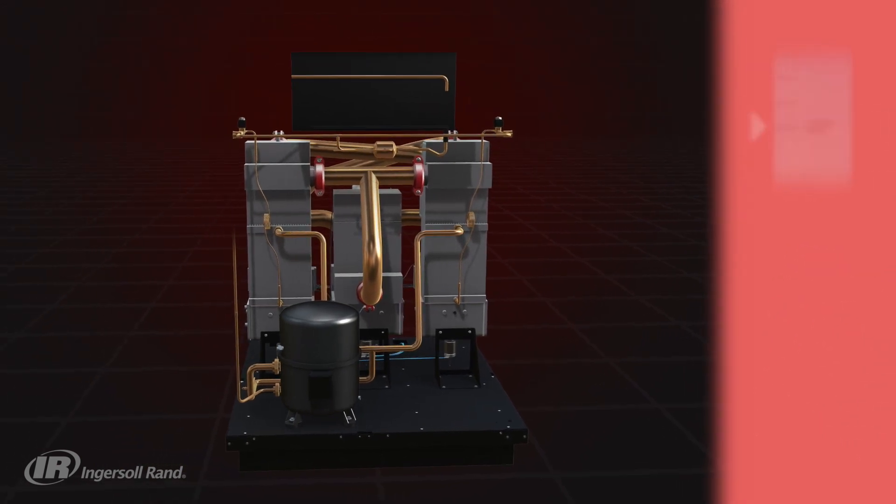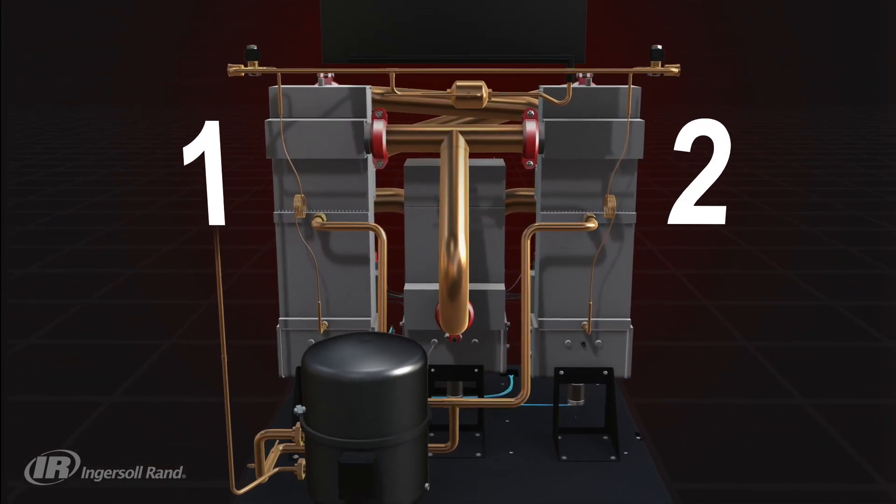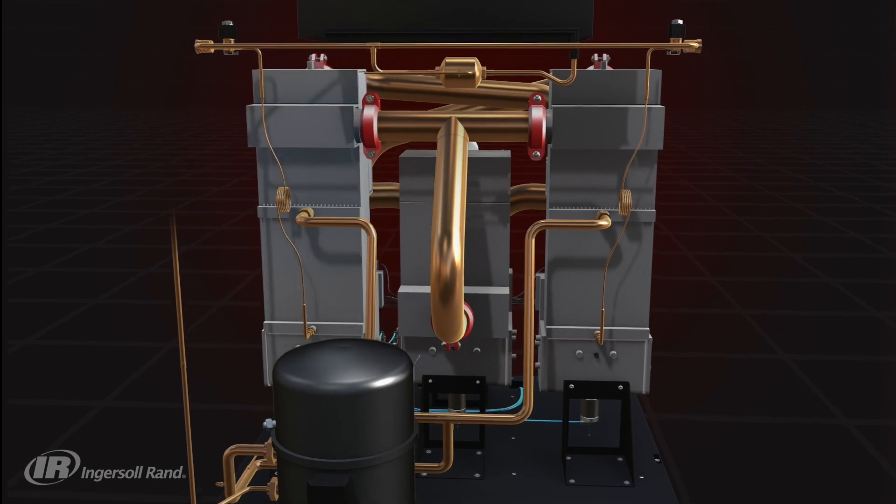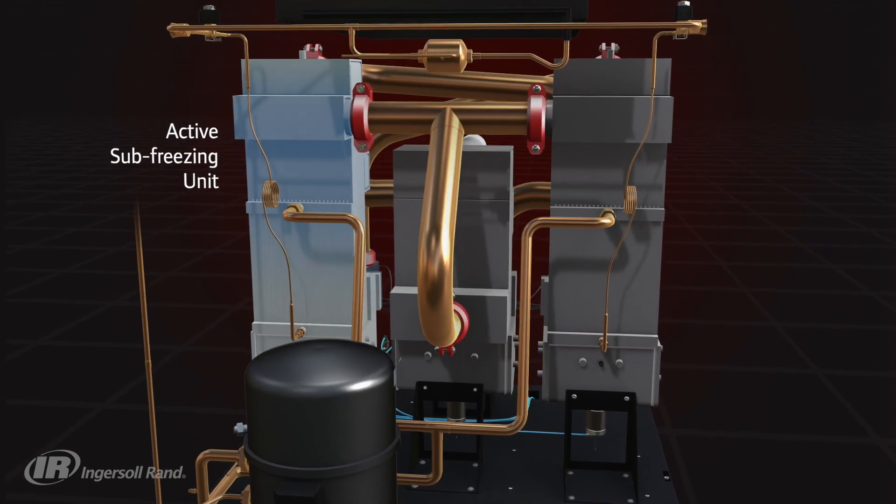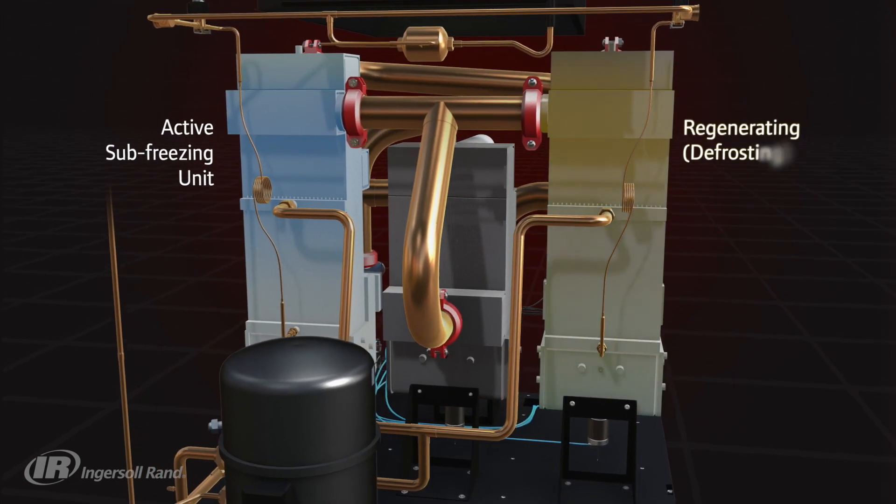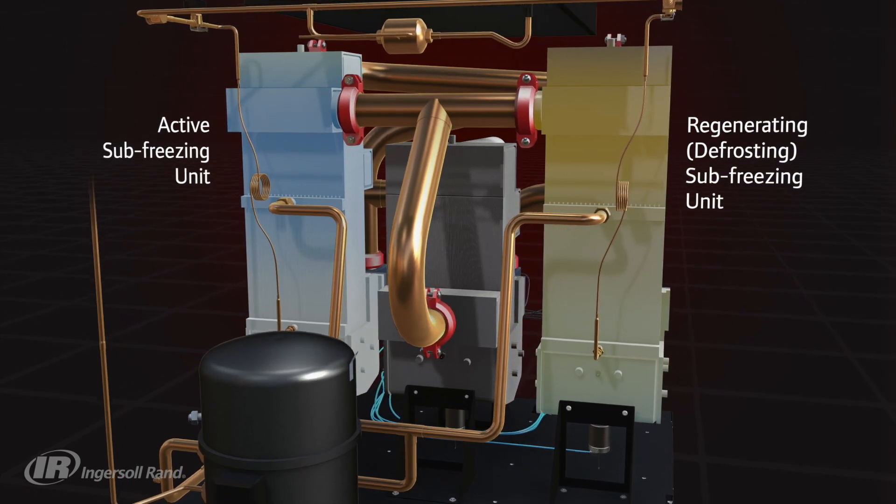At the heart of the dryer are two sub-freezing units that the drying process alternates between. So while one is actively freeze drying the air, the other is going through a defrosting cycle or regenerative phase.